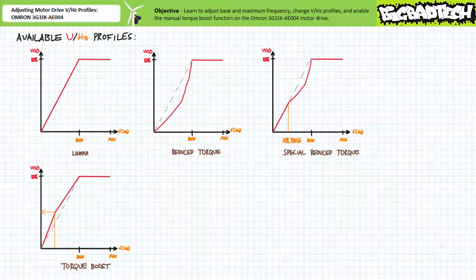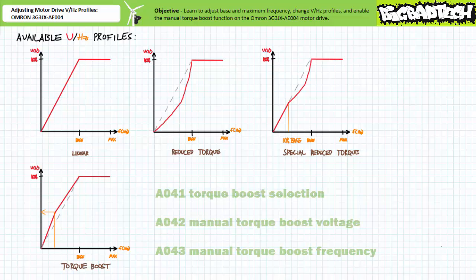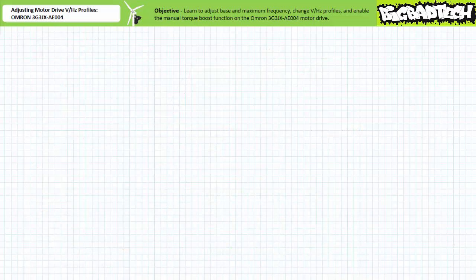To enable manual torque boost, an operator needs to check three parameters. Extended function parameter A041, torque boost selection, has two options: 00, the default, manual, and 01, automatic. Extended function parameter A042, manual torque boost voltage, is user adjustable from 0 to plus 20 percent. When set at 0 percent you've effectively got an unmodified purely linear volts per hertz profile; when you increase this setting you effectively put a dual slope kink in the volts per hertz profile. Extended function parameter A043, manual torque boost frequency, is user adjustable from 0 to 50 percent of base frequency — this is the frequency at which the knee in the dual slope occurs. Let's enable the torque boost function and call it a day.